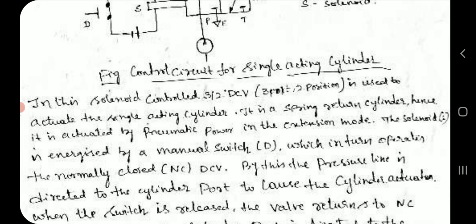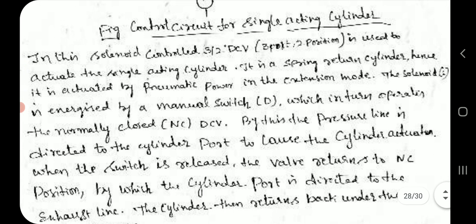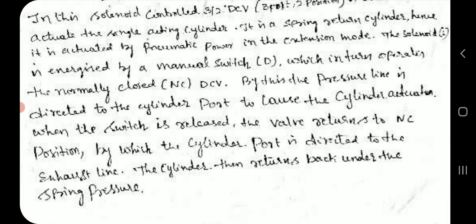Control circuit for a single-acting cylinder: A solenoid-controlled 3/2 direction control valve (three-port, two-position) is used to actuate the single-acting cylinder. It is a spring-return cylinder, so it is actuated by pneumatic power in the extension mode. The solenoid is energized by a manual switch, which in turn operates the normally closed direction control valve, directing the pressure line to the cylinder port to cause actuation.